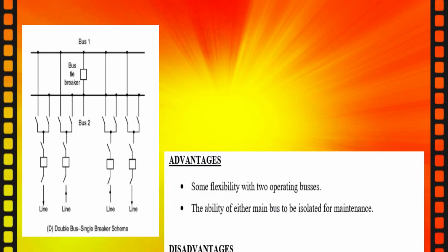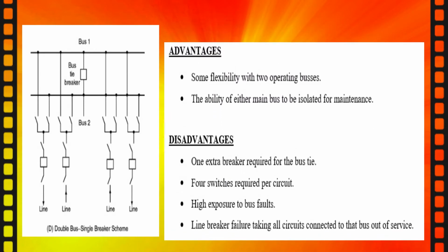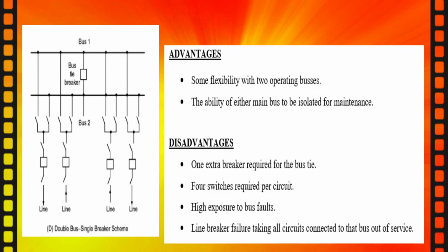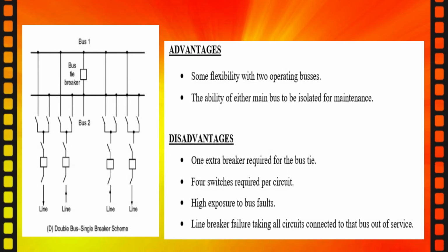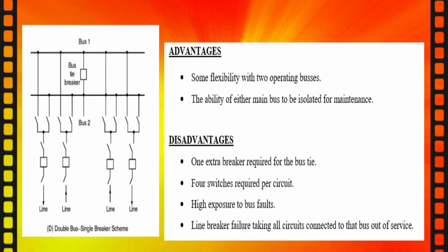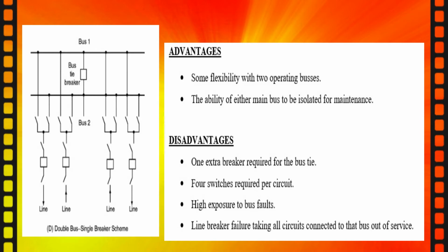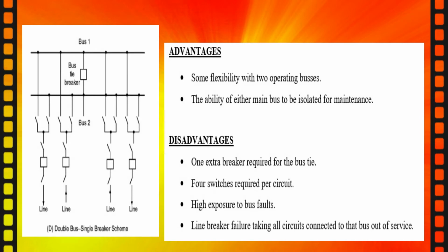Okay, the next diagram is the double bus single breaker diagram. The advantage is some flexibility with two operating buses. Then the ability of either main bus to be isolated for maintenance. Next, for the disadvantage, one extra breaker is required for the bus tie.